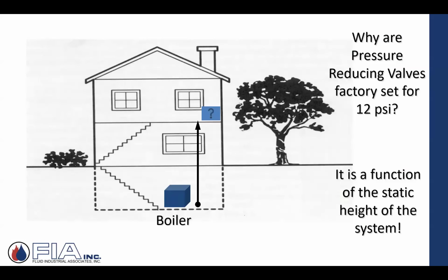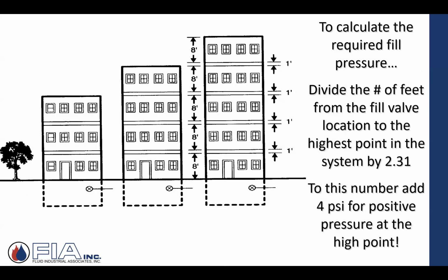So how do you set them? It's a function of the static height of the system. In this case, it's a simple little drawing, a two-story house. But whatever it takes in feet to go from wherever it's located, typically down in the mechanical room with the boiler plant, et cetera, to the highest piece of radiation or piping. It's that simple. It's that straightforward. So again, a real simple way to calculate required fill: divide the number of feet from the basement, if that's where the fill valve is, to your highest piping. What is it in feet? Divide it by 2.31. We could talk a little bit later on where that number comes from, but divide it by 2.31, and that becomes your fill pressure.